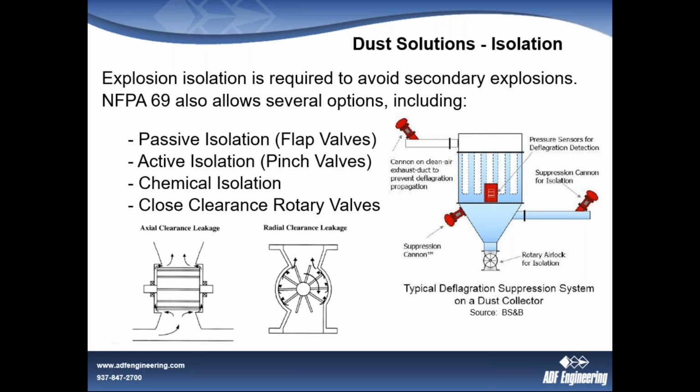It will go out your air system through the air filter, which is often found right in the middle of the room where your personnel are. And you can turn that into a flamethrower in the event of an explosion. So this is where a flap valve is a very inexpensive device that can be used to stop that and protect your personnel. There's a company out there making a pinch valve specifically for pneumatic conveying lines. It's a nice piece of equipment. It's a little expensive, though.